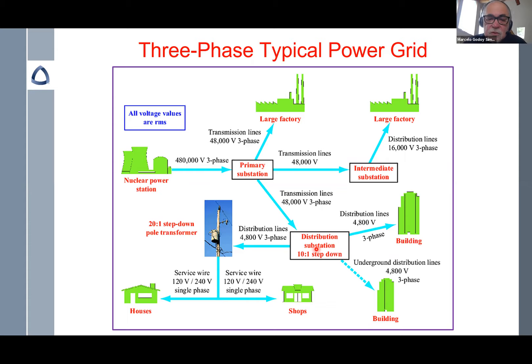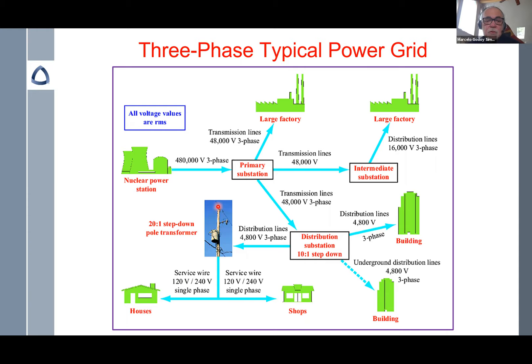We then step down the voltage at another substation for distribution to factories and large customers. In a place like Golden, Colorado, large customers include Colorado School of Mines, Coors, and the National Renewable Energy Lab. We also serve apartment buildings, residences, and offices. Distribution lines operate at around 4,800 volts, and then pole-mounted transformers step down further to 120 or 240 volts AC at 60 Hz.